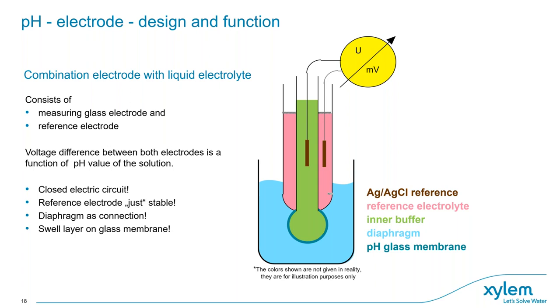For example, a blocked diaphragm would disconnect this closed circuit and effectively switch off the measurement. This can be caused by samples containing solids or proteins. Probably most electrode lifetime ends because of a non-functional diaphragm or reference. The diaphragm is a very important part of the electrode, and about 80% of electrode end-of-life comes from the diaphragm.